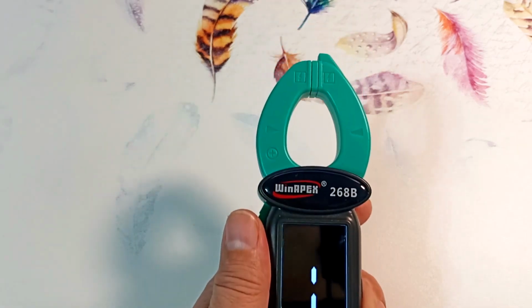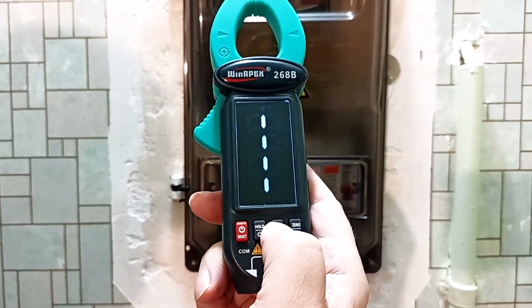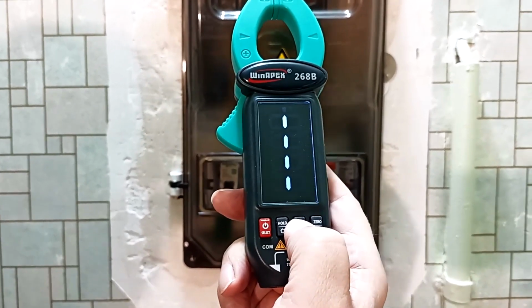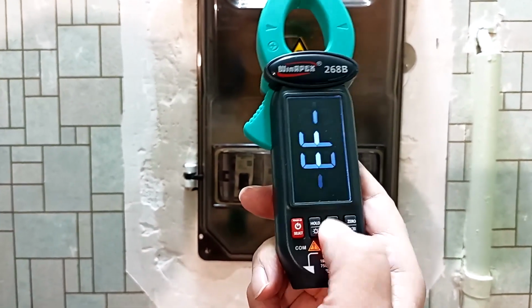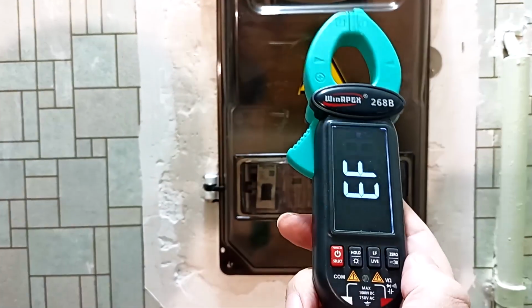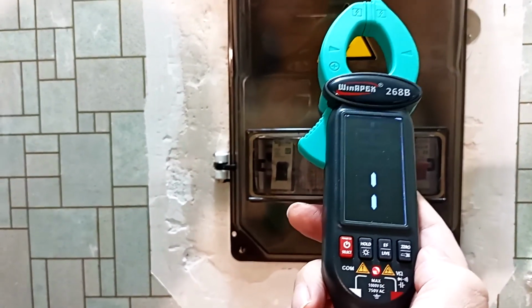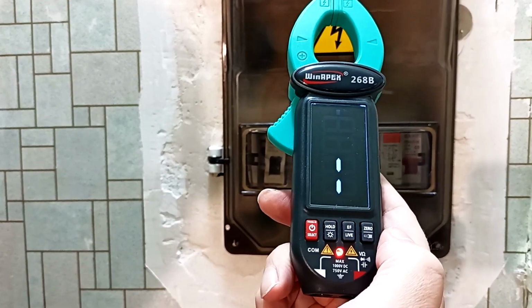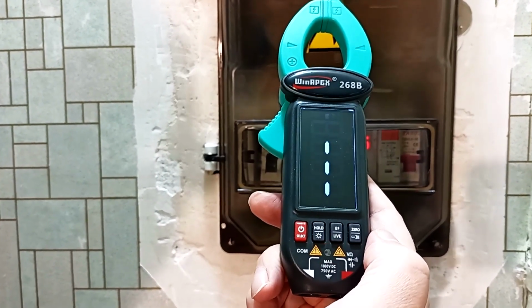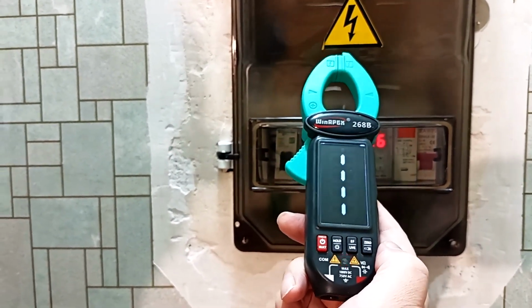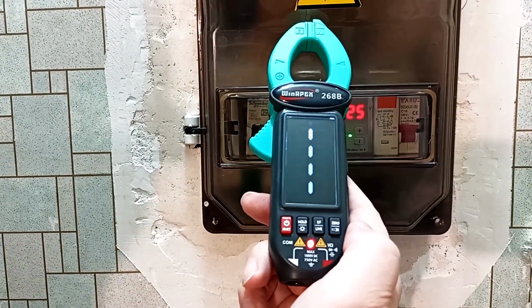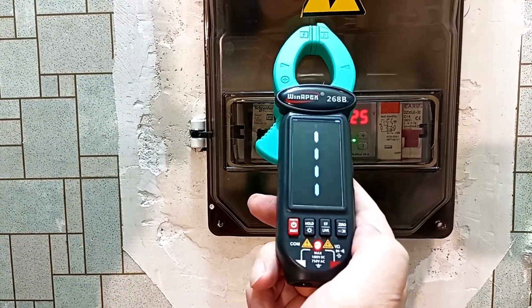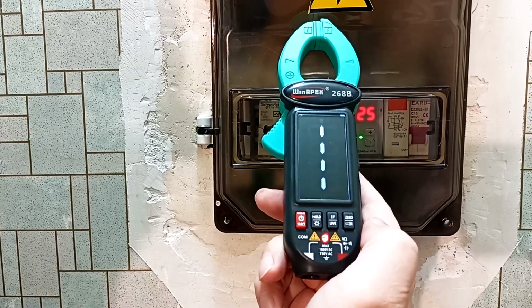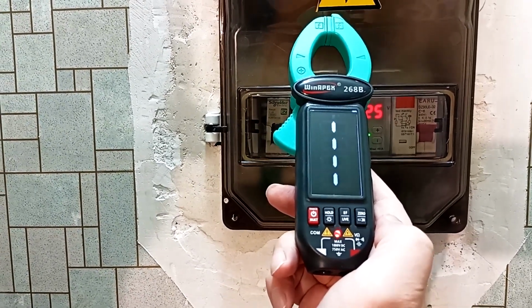To check if there is voltage in the panel, we just need to turn on the EF function and bring it to the panel. The closer we bring it, the more often the LED flashes and the buzzer sounds. So we see that there is voltage. Unfortunately, the buzzer cannot be turned off, but the buzzer in this device is rarely used.